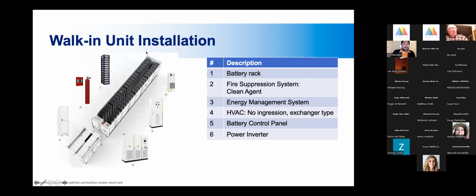This is a look at what's inside a walk-in unit. So when you see those shipping containers out there, this is what's underneath the hood. We've got the battery racks, as we learned early in the presentation. We've got the fire suppression system here, fire extinguisher. We've got the energy management system. So that's the brain here. This is the HVAC up here. This is a battery control panel. That's going to be accessible from the outside. And then we've got the inverters here, which are over with the energy management system. What the inverters do, for folks who don't know, is change DC or direct current to AC or alternating current.